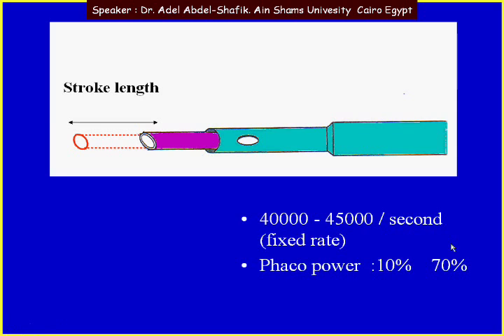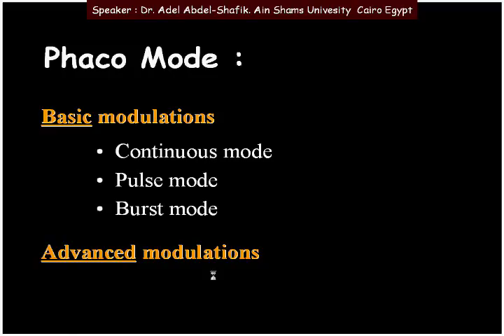Each machine has a fixed rate of vibration. The tip of the phaco needle can vibrate forward and backwards at a fixed rate for each machine. When we choose a power of 10 or 70%, we change the stroke length. At high powers like 70 or 80%, we get a long stroke length; at low powers like 10%, we get a short stroke length. We can modify the amount of power by choosing a certain percentage, and for each percentage we change the stroke length.